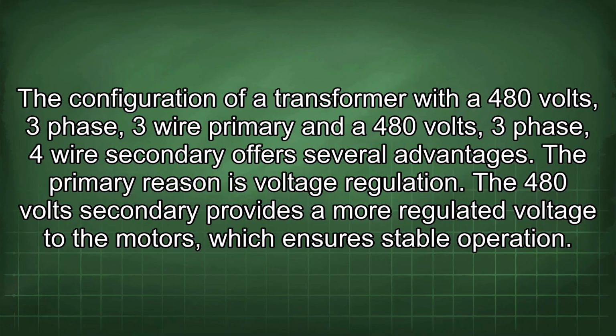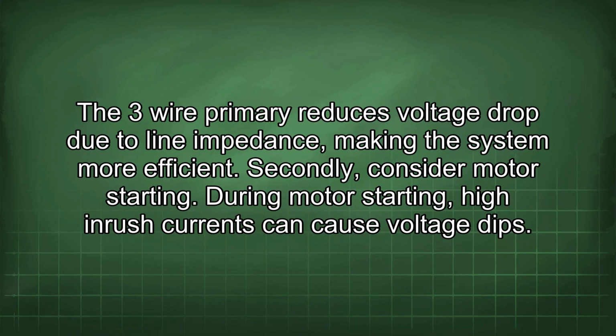A configuration of a transformer with a 480 volts, 3-phase, 3-wire primary and a 480 volts, 3-phase, 4-wire secondary offers several advantages. The primary reason is voltage regulation. The 480 volt secondary provides a more regulated voltage to the motors, which ensures stable operation. The 3-wire primary reduces voltage drop due to line impedance, making the system more efficient.